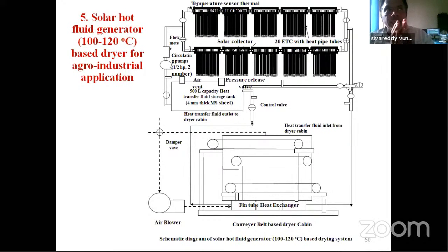We store that hot fluid in a storage tank. In the dryer, as I mentioned, there is free moisture and bonded moisture. When bringing bonded moisture to the surface, the relative humidity of air does not increase much, so we can recycle the same hot air. Earlier there was no option to recycle the energy, but now we can store the recycled air's energy in storage tanks, enhancing drying time.